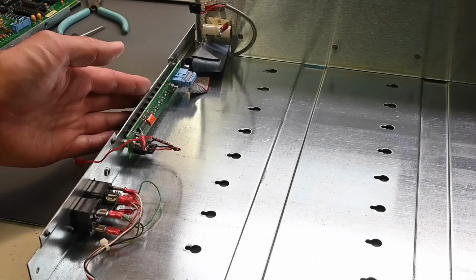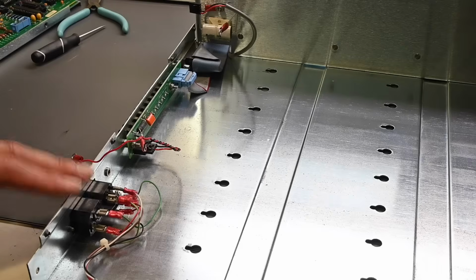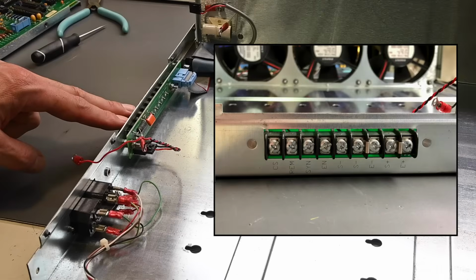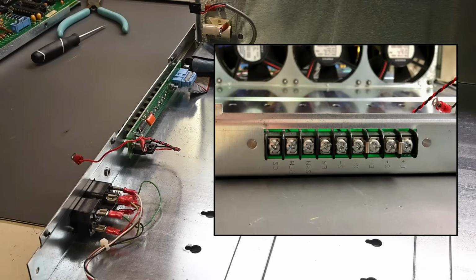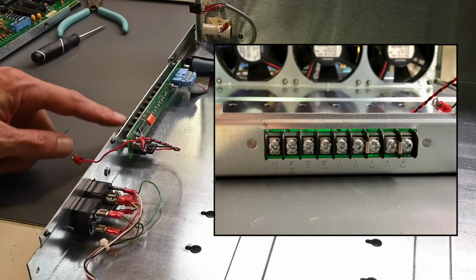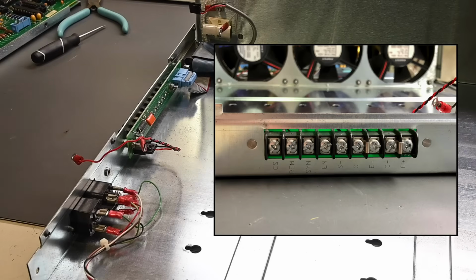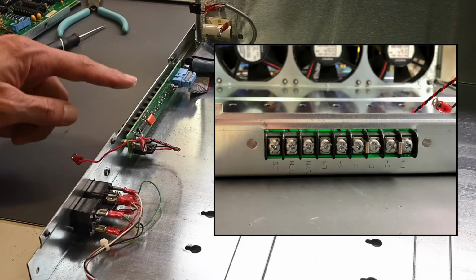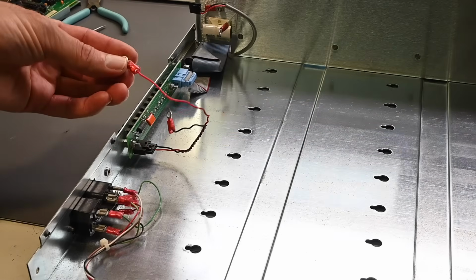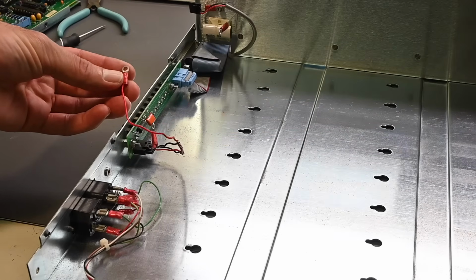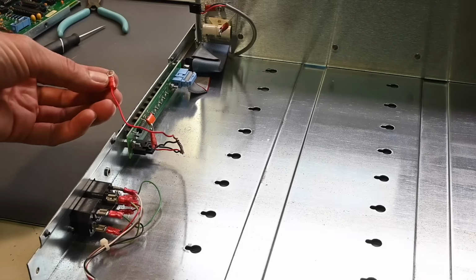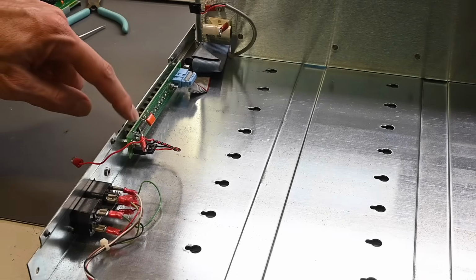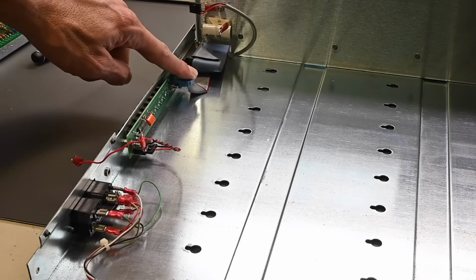So at the back of the electronic load, along this lower edge, the AC line input and a voltage selector switch. There's a terminal board right here for some external connections that can be made. One of the connections is for the voltage sensing, so there's some jumpers. If you remove those jumpers, then you can remote voltage sense, but with these jumpers in place, then the voltage sensing is done inside the electronic load. It's off of these wires, so these connect to the positive and negative distribution buses, which I'll make that connection later on. And then everything on this board goes off on this ribbon cable.